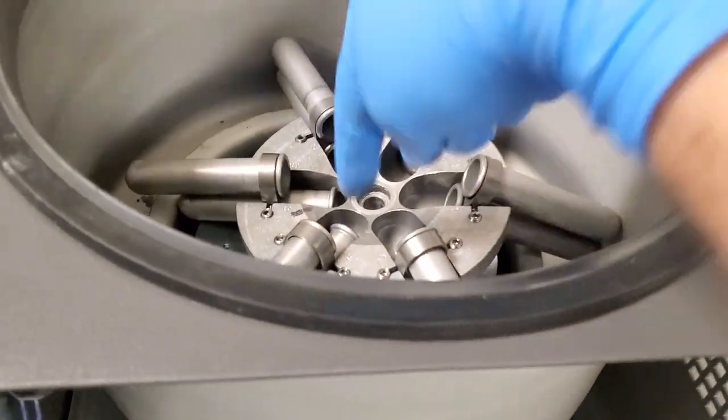Here's the interesting thing about this type of centrifuge: it does not have a wobble detect or out-of-balance sensor. What it does is it relies on the RPM of the rotor at a certain time, or a certain amount of pulses. It pulses to the motor and expects a certain RPM that will tell you if you got the correct rotor in and if there's any other problems.